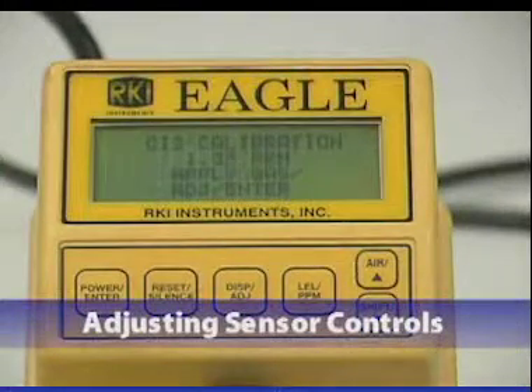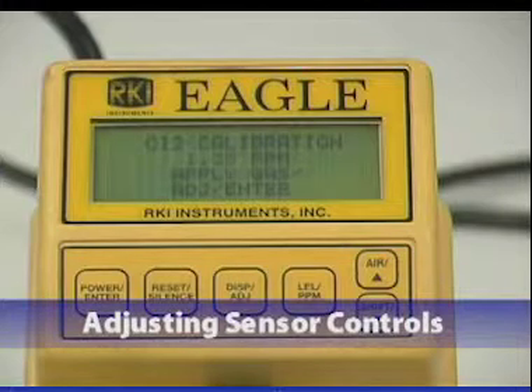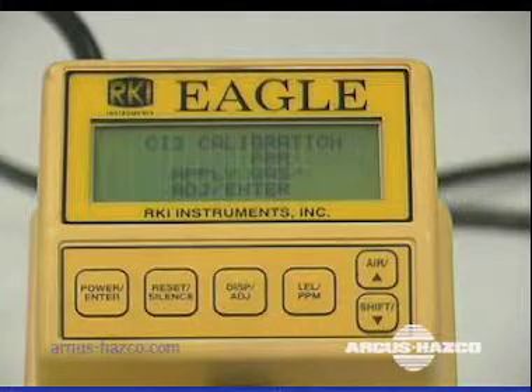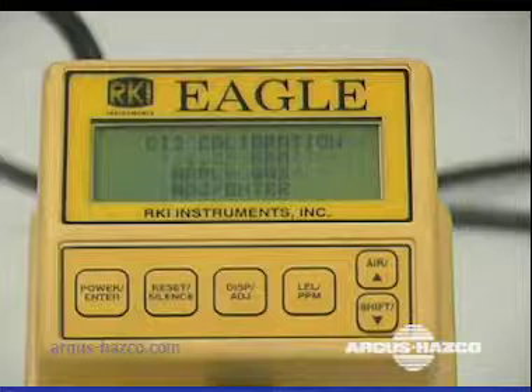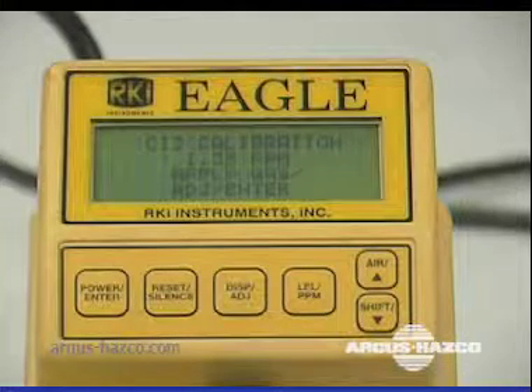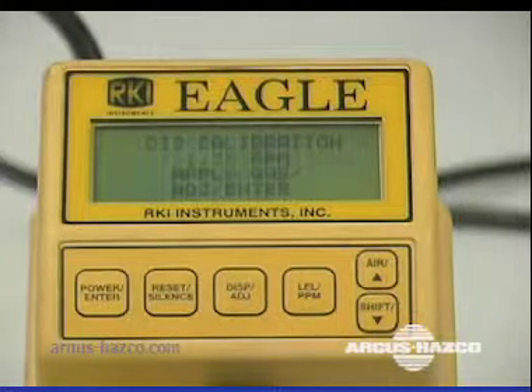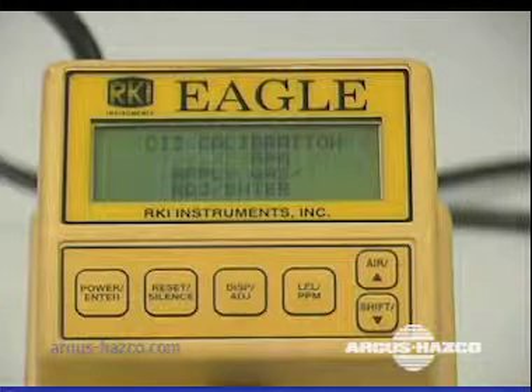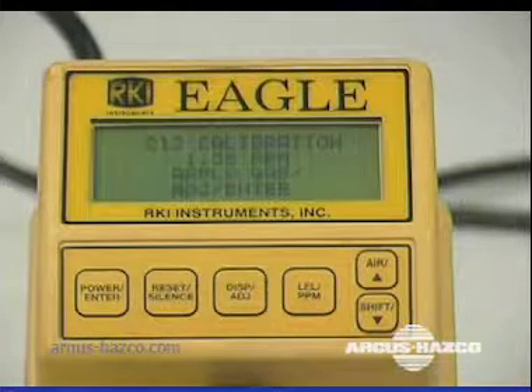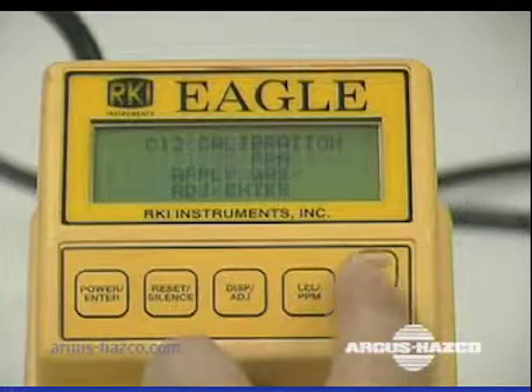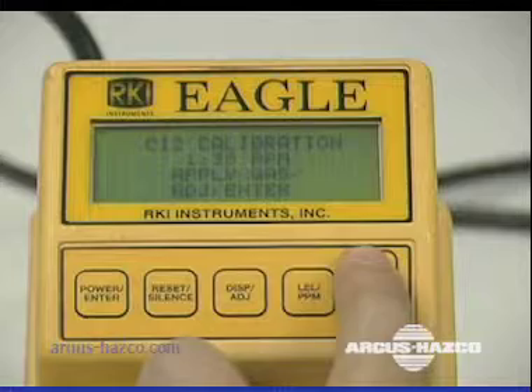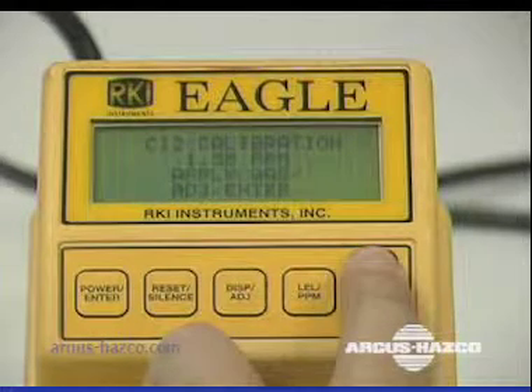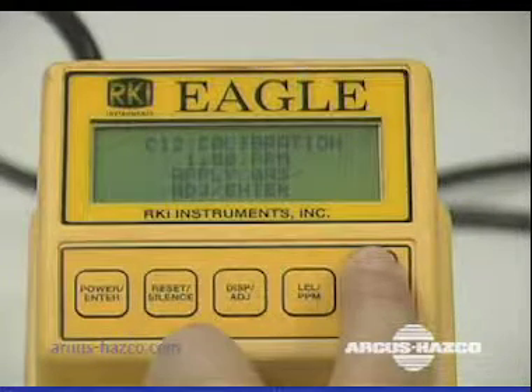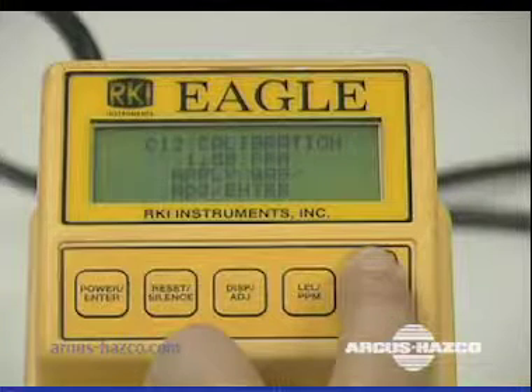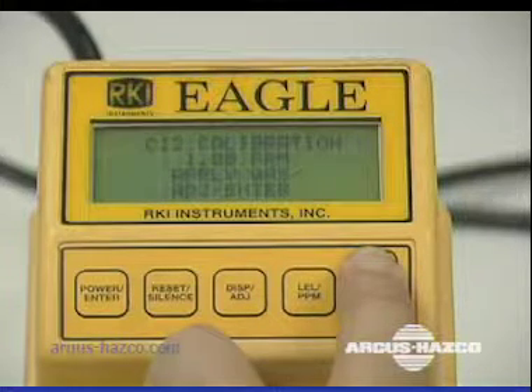If you are unable to match the reading to the concentration of the cylinder, you will need to adjust the sensor controls. Only perform these steps if you are unable to set the correct calibration reading with the up or down buttons. Before exiting the single calibration mode, use the up or down buttons to set the reading to the middle of the range in which you can currently adjust. For example, if you can set the reading from a minimum of 0 ppm to a maximum of 2 ppm, set the display to 1 ppm.